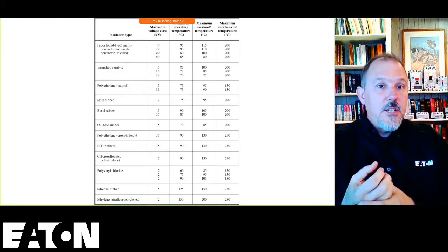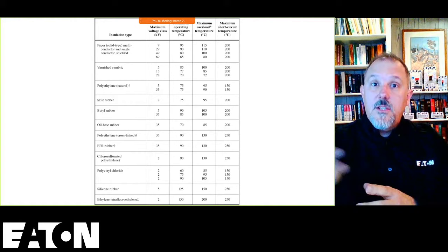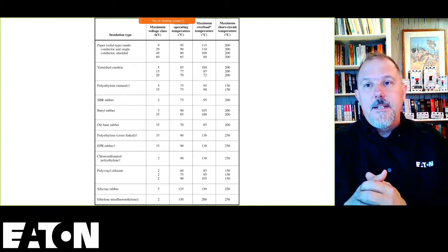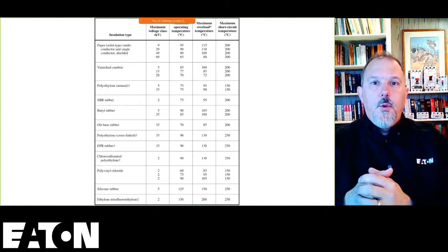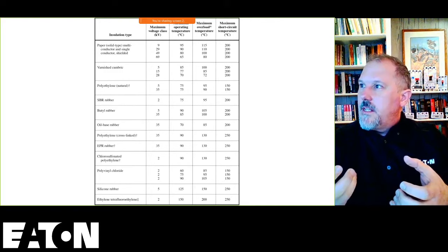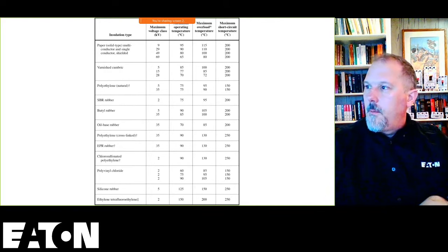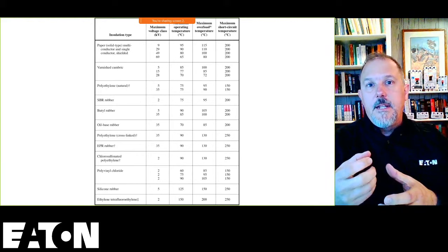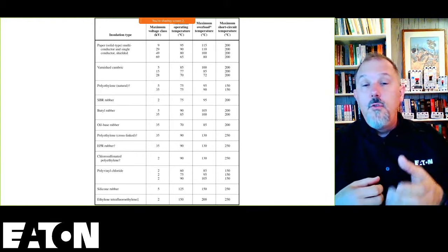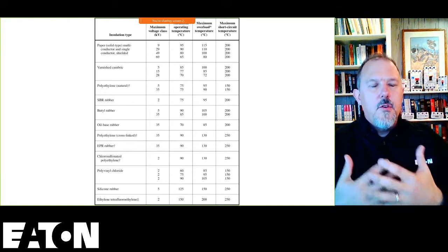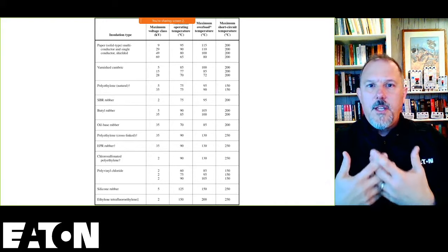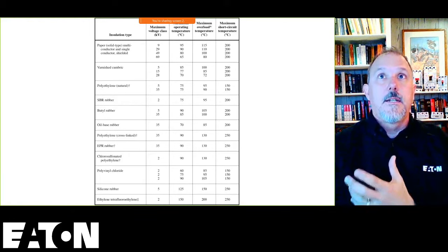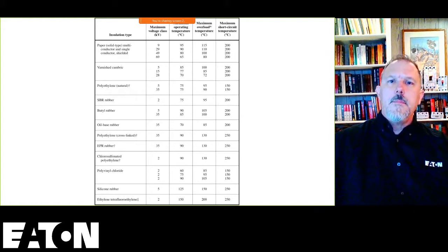But most of these conductors are going to have an insulation around them, and that insulation serves a couple of purposes. One, it insulates us from touching it. It also provides protection for that conductor, etc. But if you think about copper versus a rubber insulation, or oil-based rubber, or polyethylene, or EPR, all of these different types of components, those materials that surround that conductor will melt well before you melt the copper. So when we look at thermal damage curves, you're looking primarily at heating that conductor to a point where it damages the insulation, if that makes sense. All right.